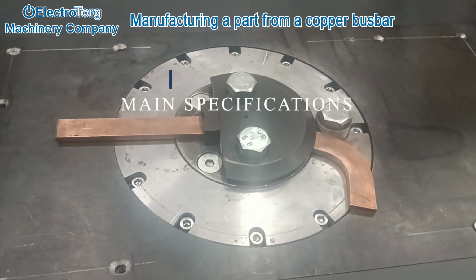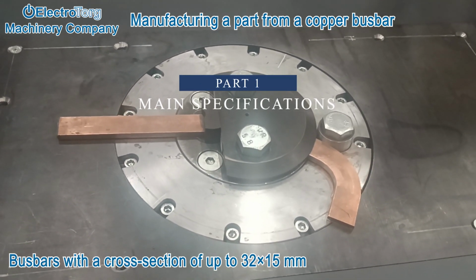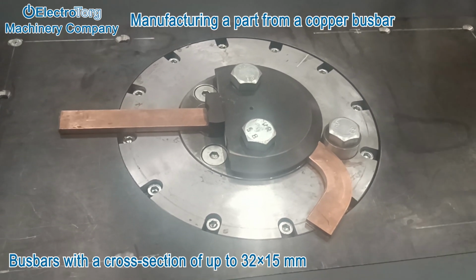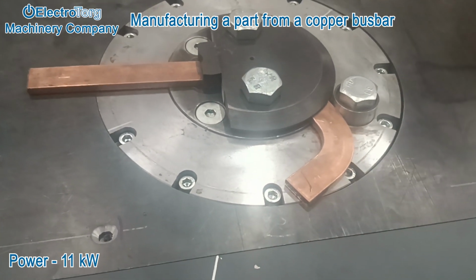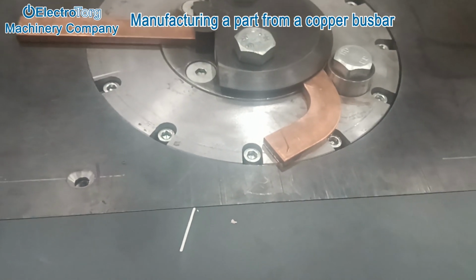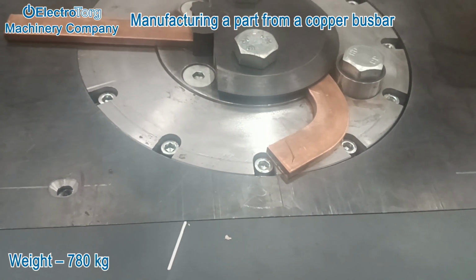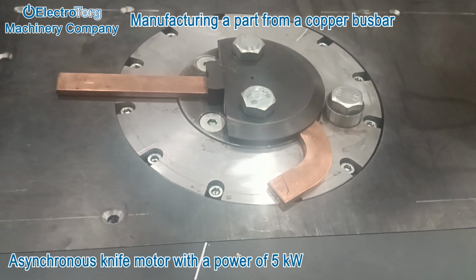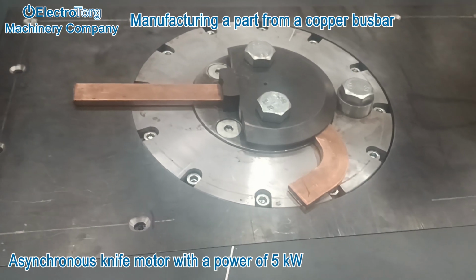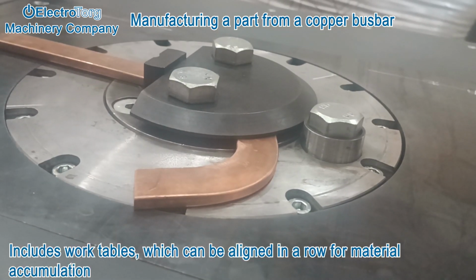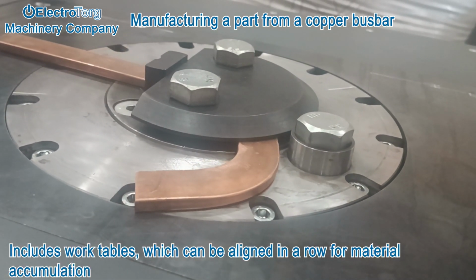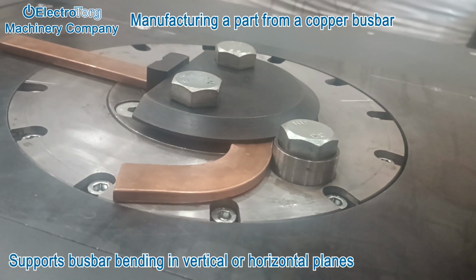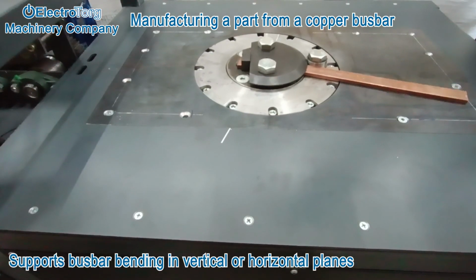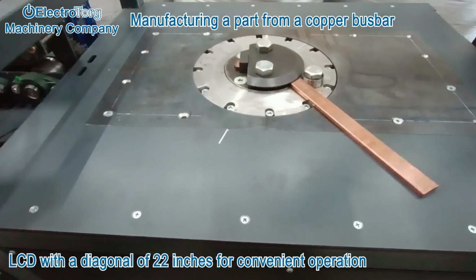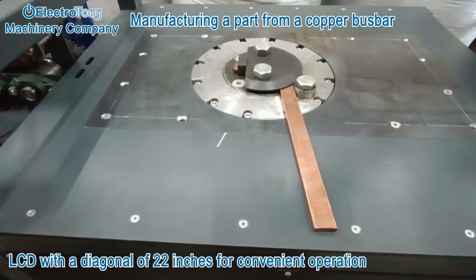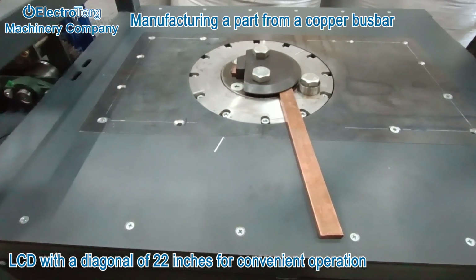The machine can be integrated into conveyor lines and automate production processes. Main specifications: works with bus bars with a cross-section of up to 32 by 15 mm. Power: 11 kilowatts. Weight: 780 kilograms. Asynchronous knife motor with a power of 5 kilowatts. Includes work tables which can be aligned in a row for material accumulation. Supports bus bar bending in vertical or horizontal planes. Liquid crystal display with a diagonal of 22 inches for convenient operation.